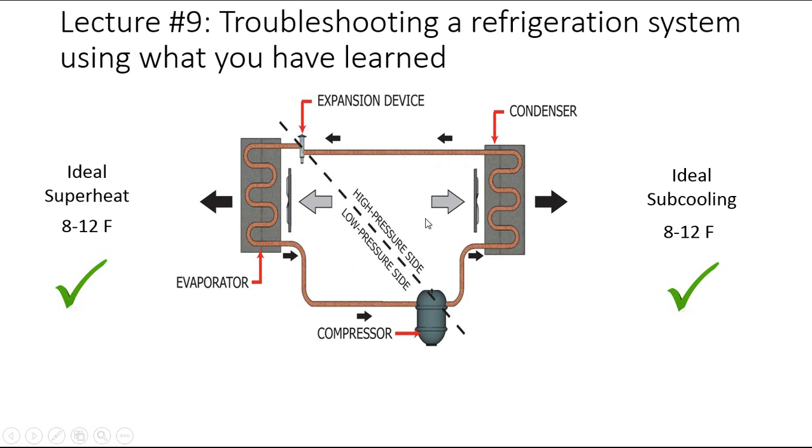Let it run for 5 minutes, then check your superheat and subcooling and see what you come up with. In the next slide, we're going to talk about some really interesting stuff—what happens if your system is out of balance.